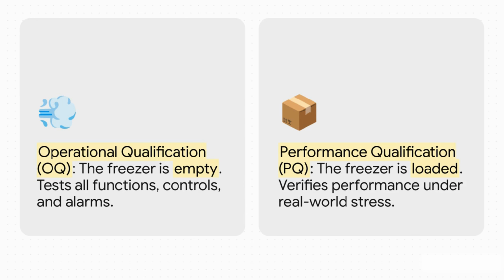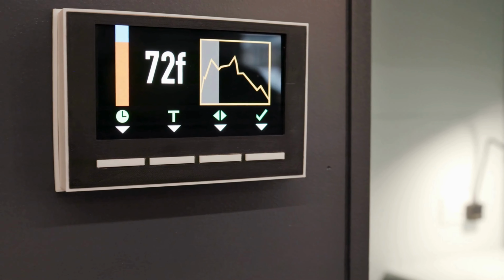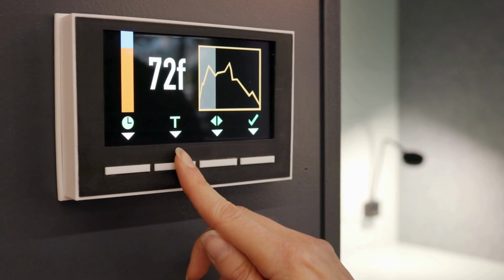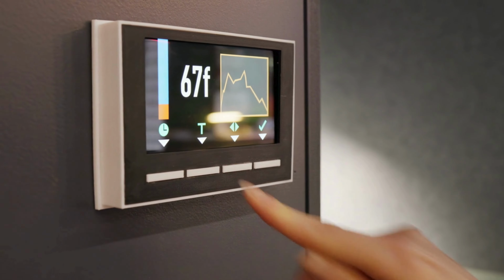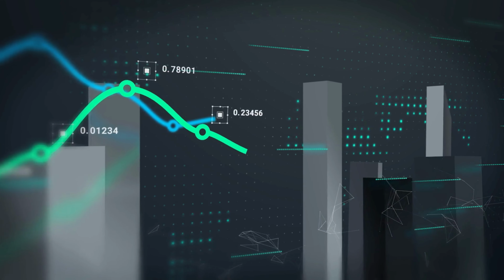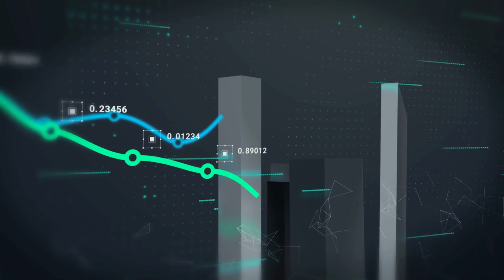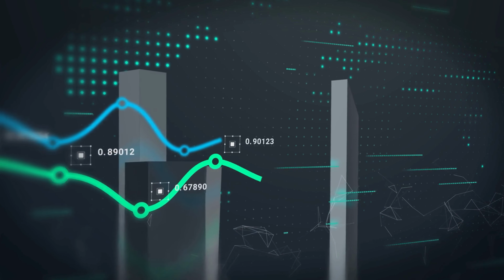The freezer is now loaded with either the real product or something that simulates it, and you're verifying that it performs consistently under the stress of real-world conditions. You know, people opening doors, daily use. Empty versus loaded. That is the key difference. Right, so how in the world do you gather all the data to prove performance during OQ and PQ? I mean, you can't just trust the little number on the front of the door. You literally have to map what's invisible.